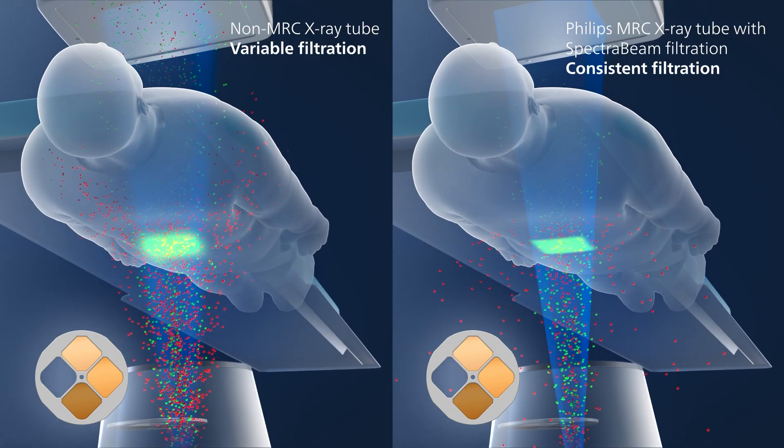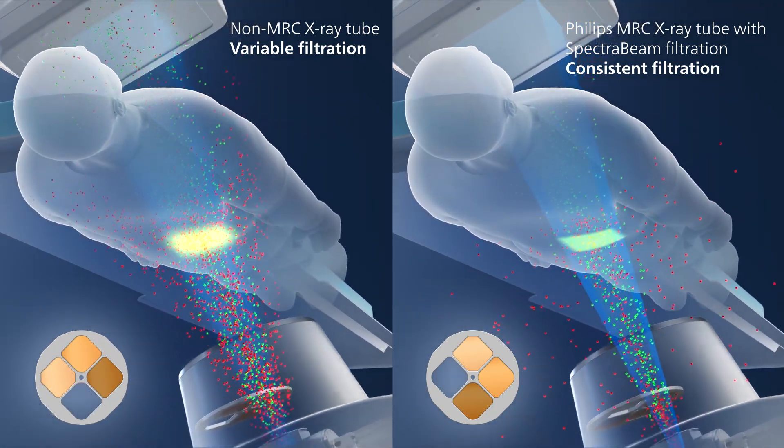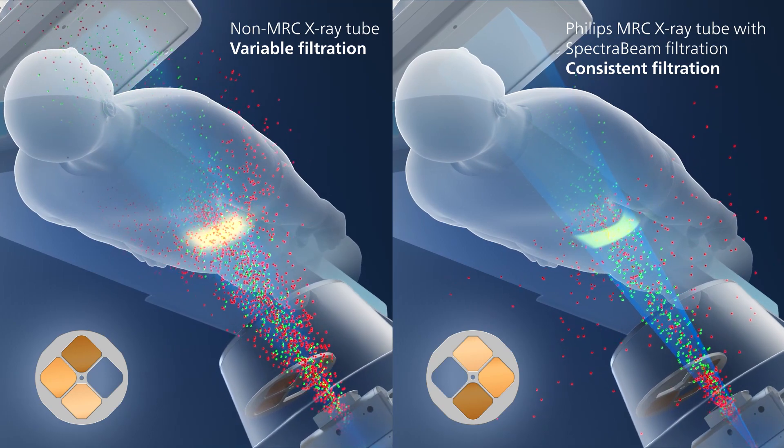Automatically adjusting filtration as part of the dose rate control leads to an unpredictable and higher skin dose, as well as inconsistent image quality.